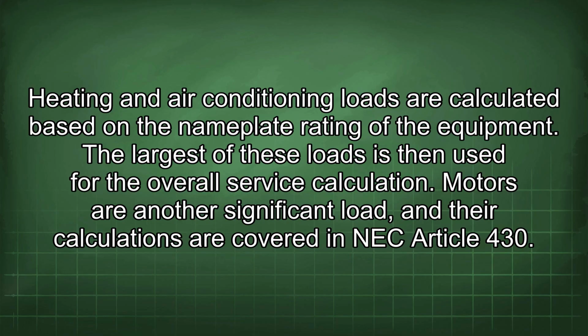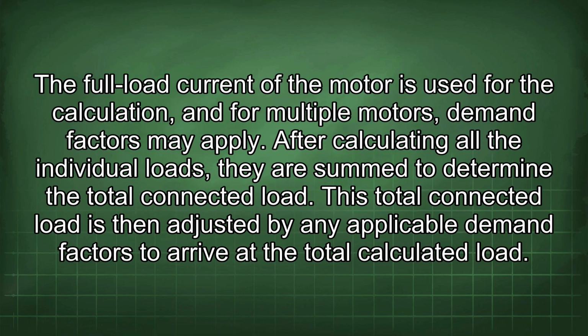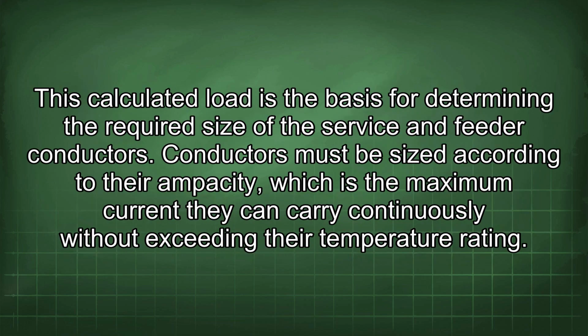Motors are another significant load, and their calculations are covered in NEC Article 430. The full load current of the motor is used for the calculation, and for multiple motors, demand factors may apply. After calculating all the individual loads, they are summed to determine the total connected load. This total connected load is then adjusted by any applicable demand factors to arrive at the total calculated load. This calculated load is the basis for determining the required size of the service and feeder conductors.